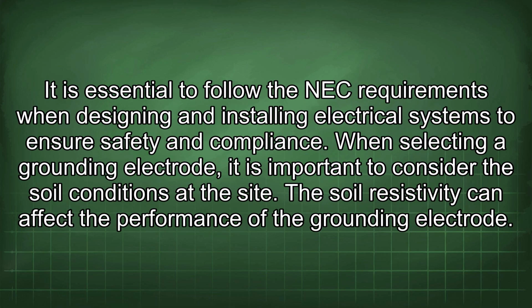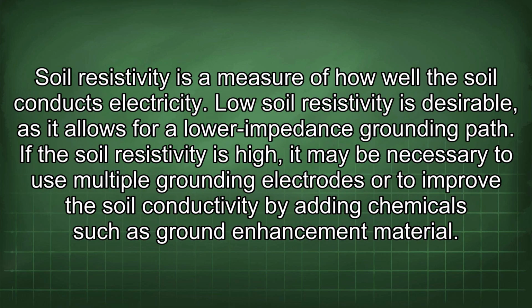It is essential to follow the NEC requirements when designing and installing electrical systems to ensure safety and compliance. When selecting a grounding electrode, it is important to consider the soil conditions at the site. The soil resistivity can affect the performance of the grounding electrode. Soil resistivity is a measure of how well the soil conducts electricity. Low soil resistivity is desirable, as it allows for a lower impedance grounding path.